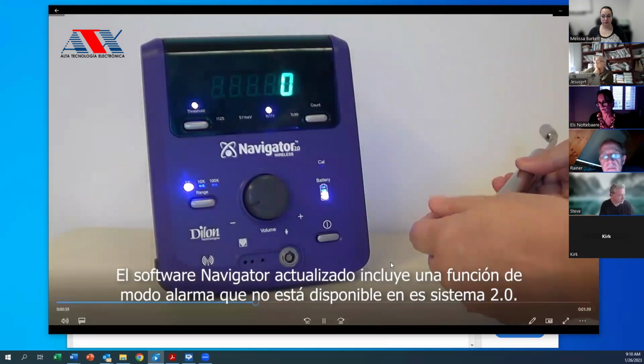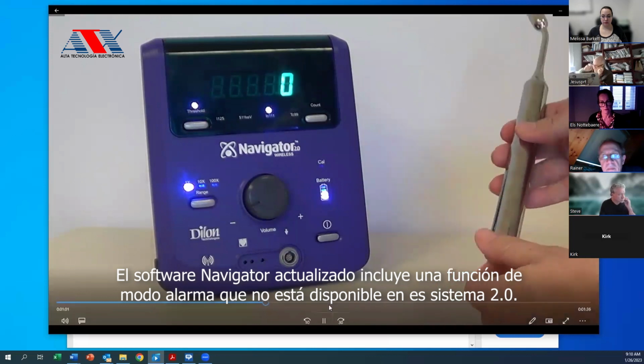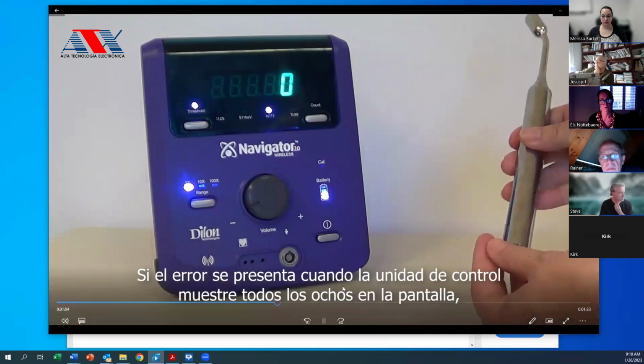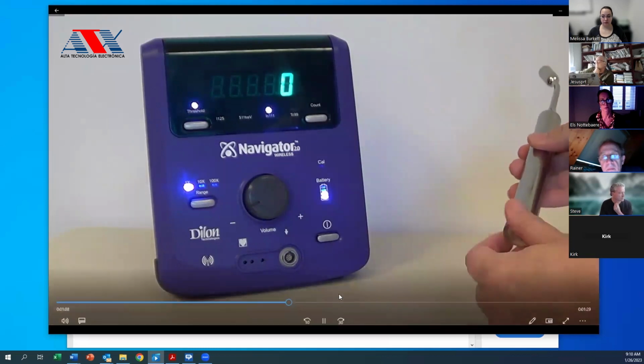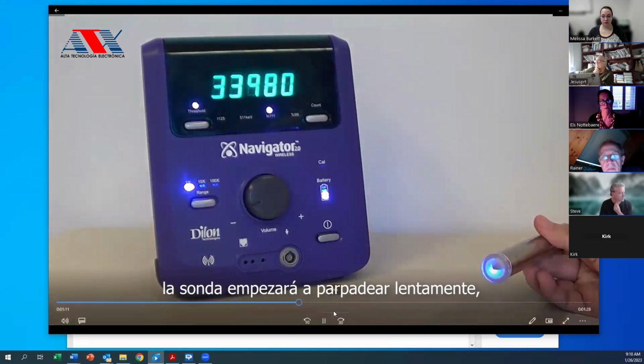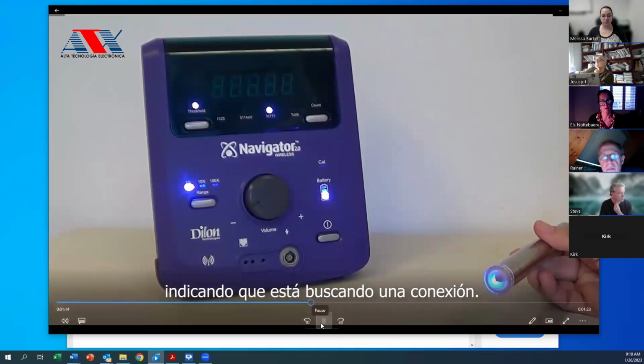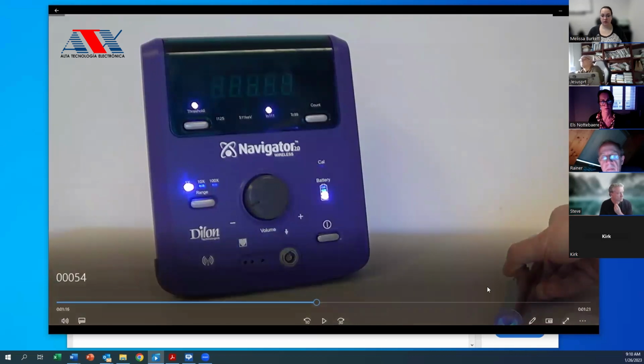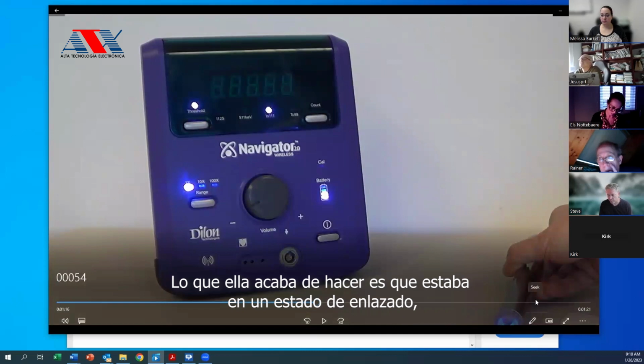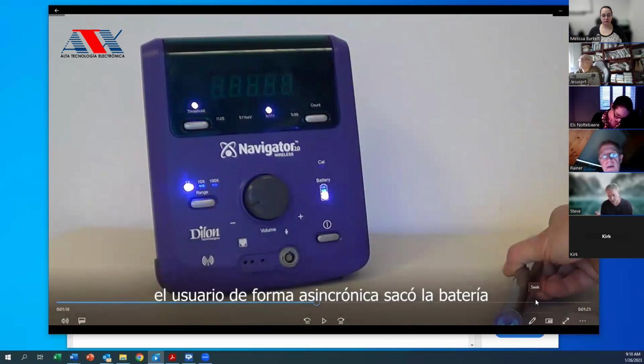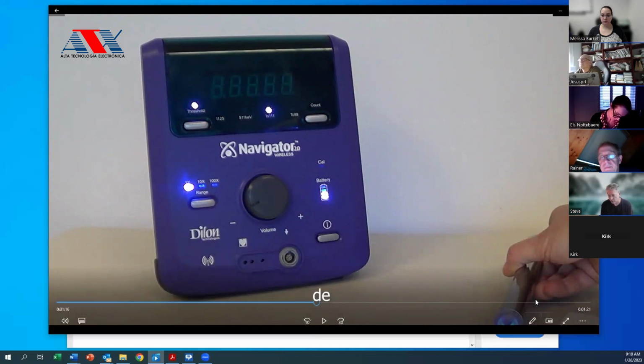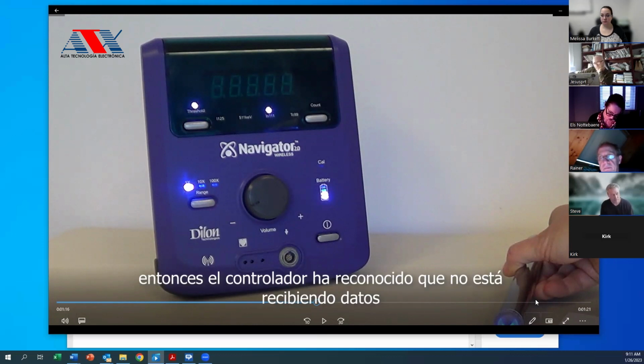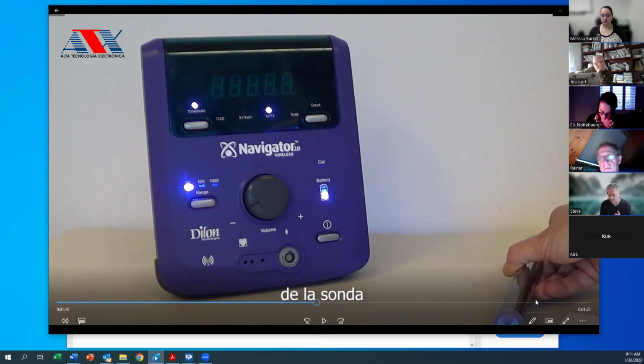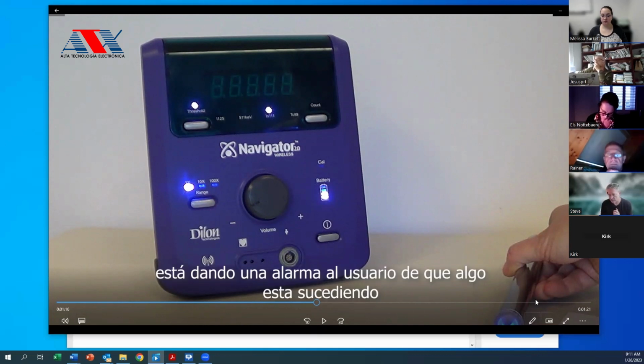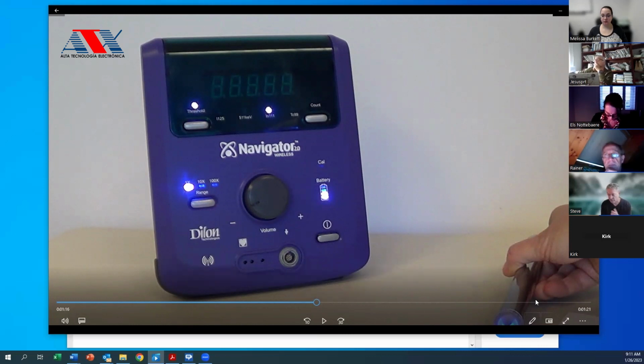The Navigator upgraded software includes an alarm mode feature not available in the previous system. The error presents when the control unit displays all eights on the screen. The probe will begin slowly flashing, indicating it's looking for a connection. So what she just did is, they were in a paired state, and the user asynchronously pulled the battery out of the probe. The controller didn't expect that, so it recognized that it's not receiving data from the probe, and it's raising an alarm to the user that something unexpected has happened.